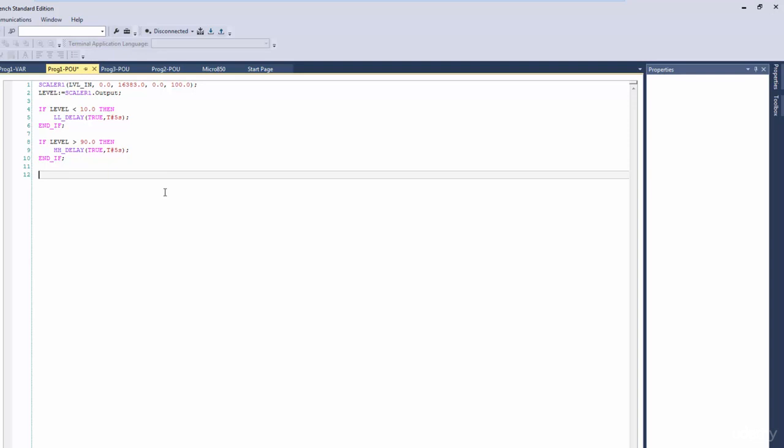So that being the case, that means we have to do something hinky to do the same effect. So let's see what we can do. We're going to say if, and then we know we want to look at our low delay, LL underscore delay. And then we can dot, and we know we want Q, because that's what it's called in CCW when the timer times out. So if LL delay dot Q, that means this thing is timed out, then what do we want to do?